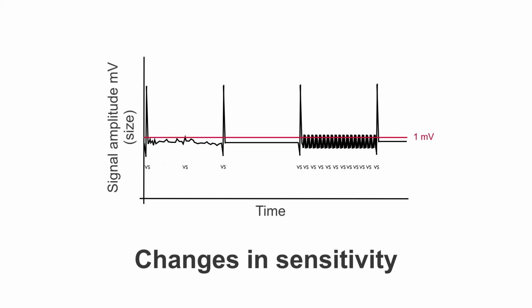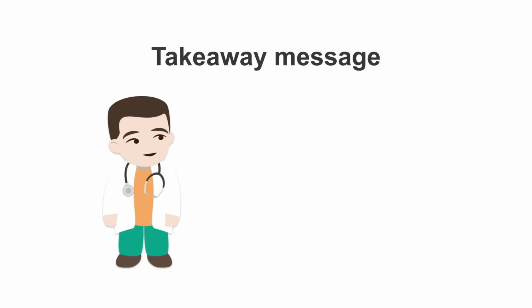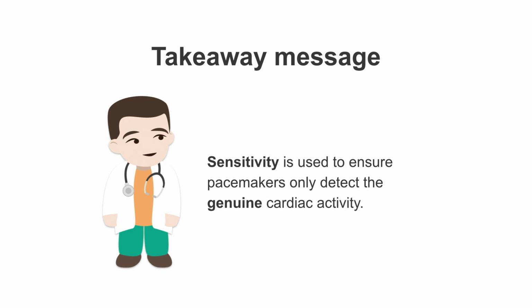Alternatively, if you reduce sensitivity, you make the device more sensitive. You can see that actually now some of this muscular artifact's being picked up and all of this electromagnetic interference is being registered once more because we have reduced the sensitivity to 1 millivolt. So, the takeaway message: sensitivity is used to ensure pacemakers only detect the genuine cardiac activity.